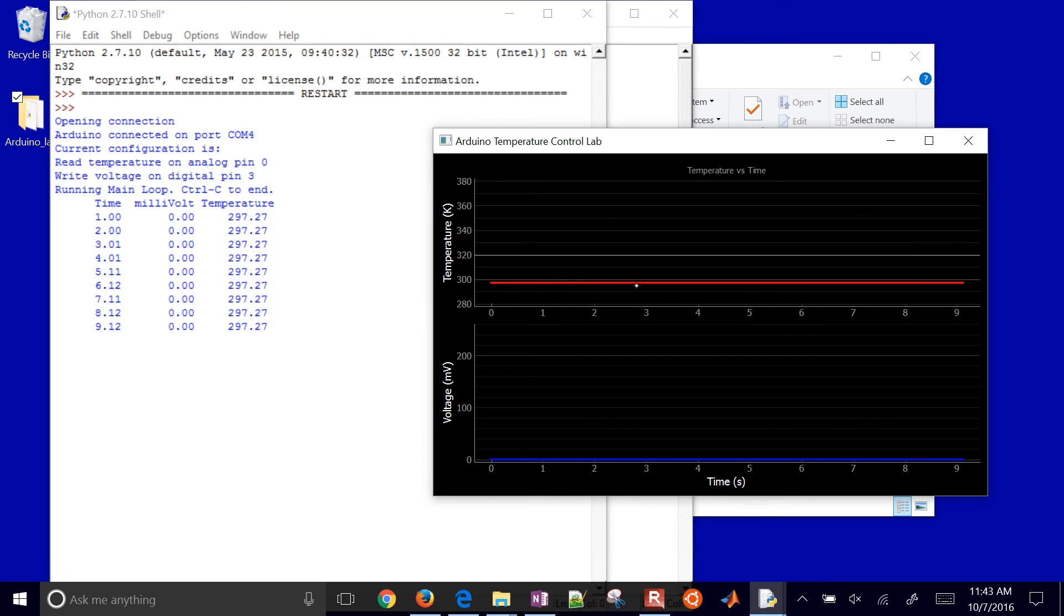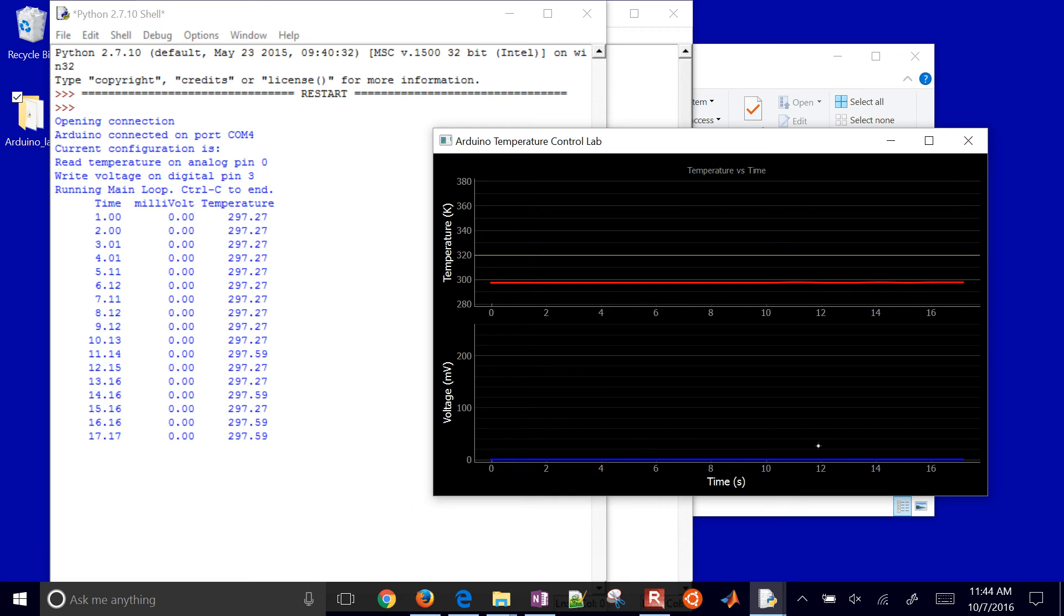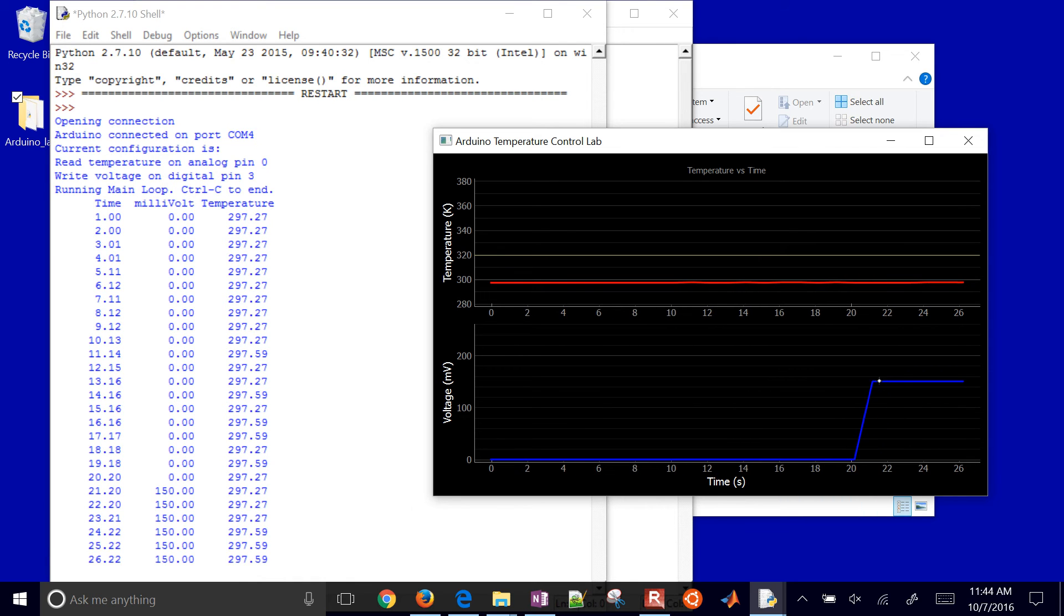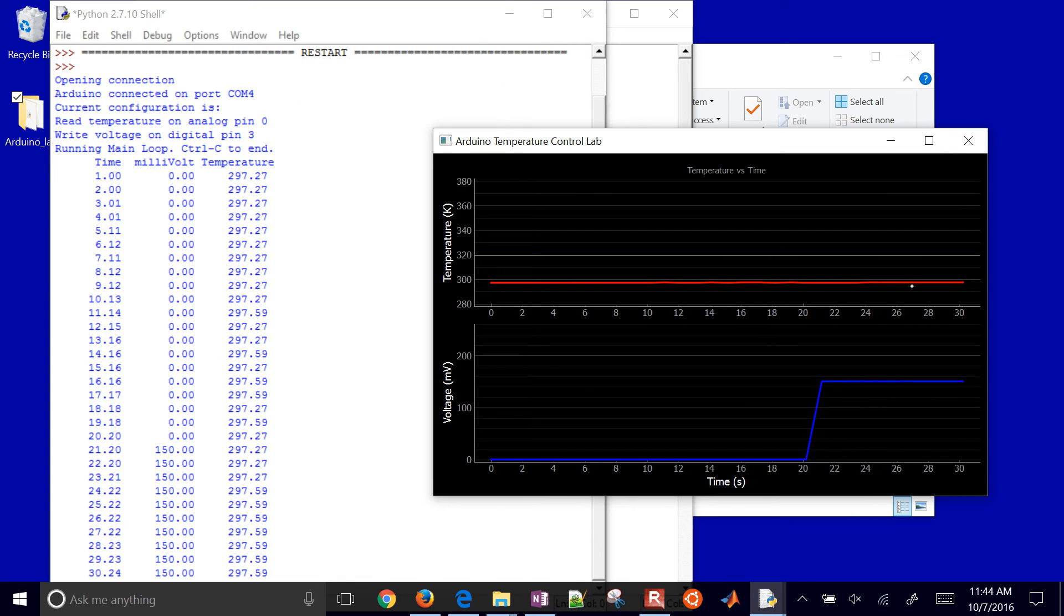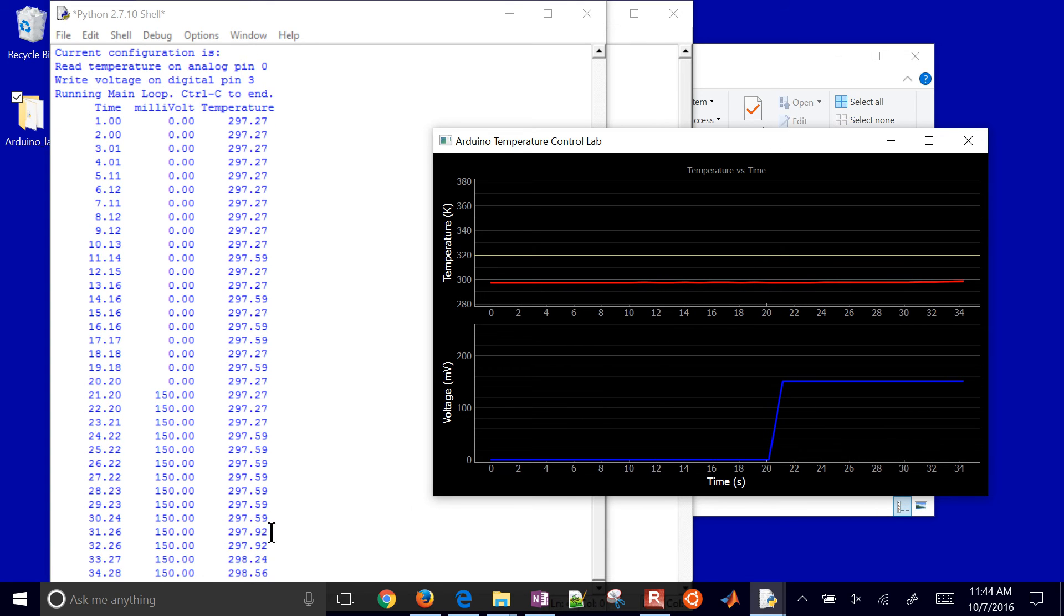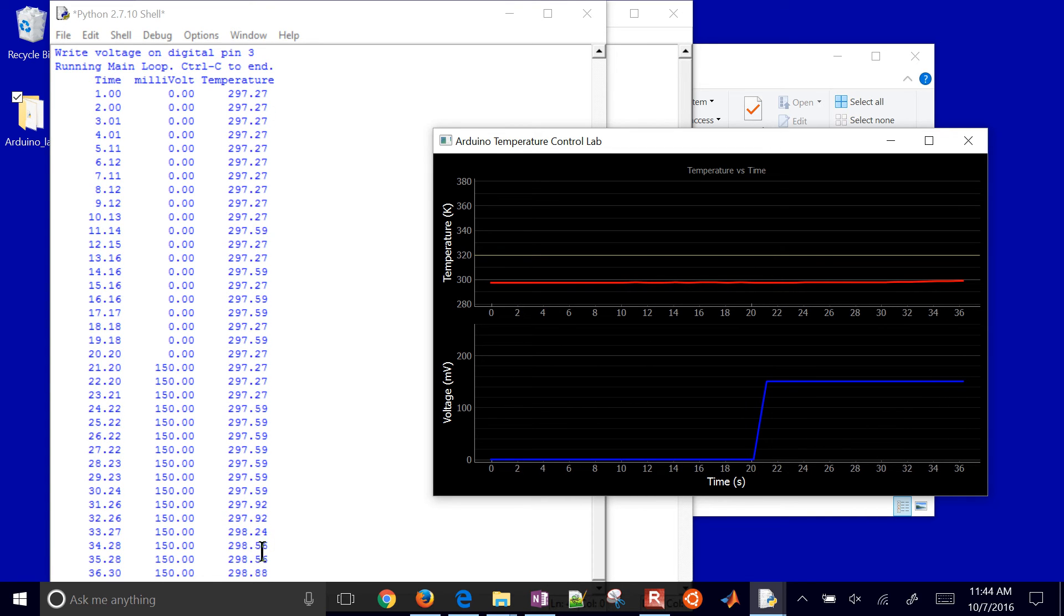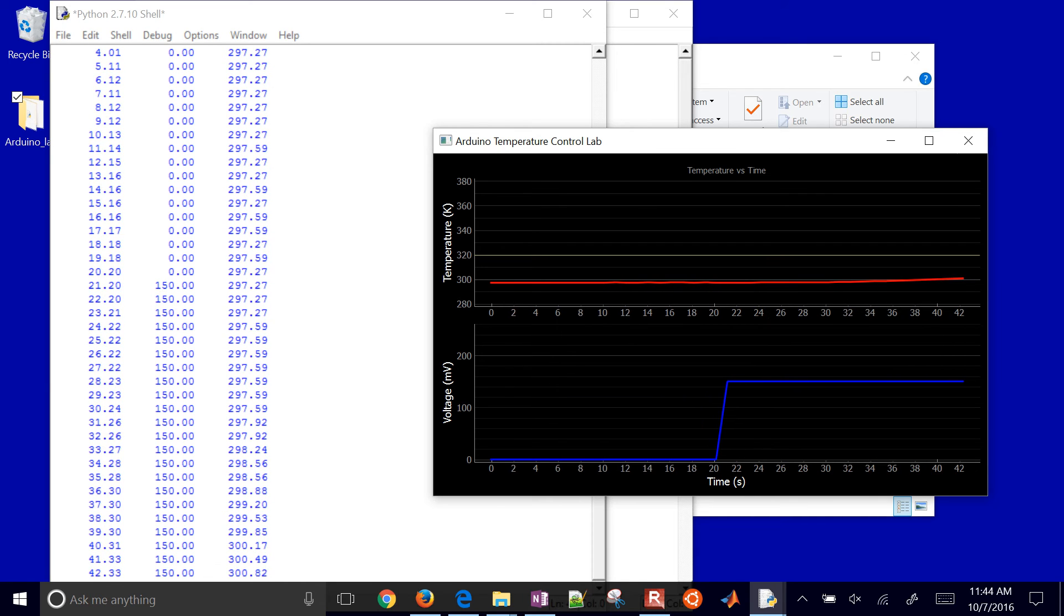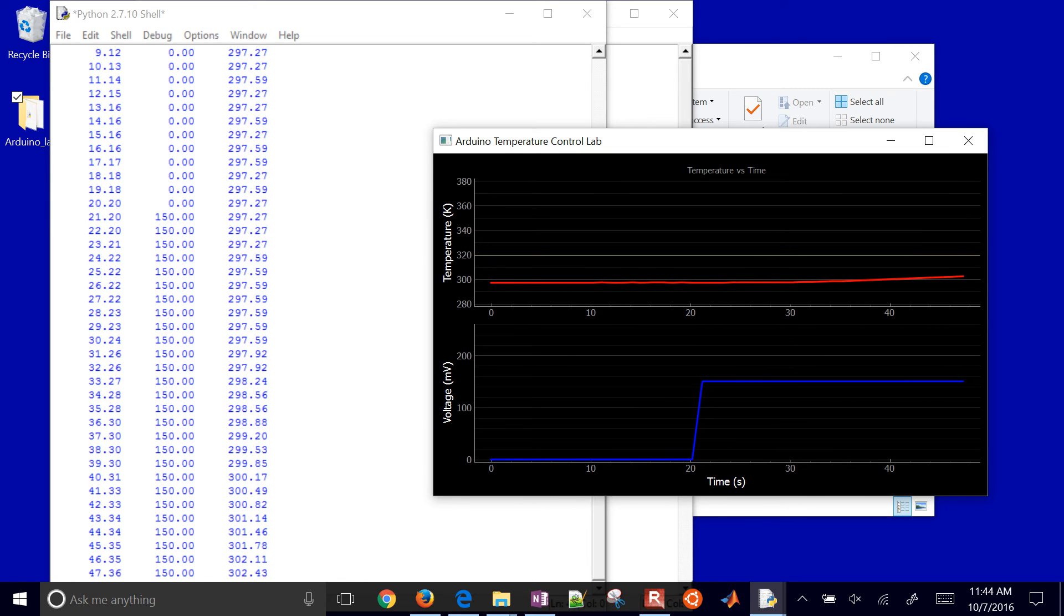And then it'll have this plot that starts up right here. You'll be able to see the red line. The red line is going to be your current temperature. The blue line is your millivolt signal. So if you either have a controller change that or you change it, the blue line is going to be your millivolt, and that just went from zero up to 150. And then what we'll see is we'll start to see this temperature rise. So you can see right here the temperature just went up by a degree. It's going up just ever so slightly there. You can see it rise just above 300, and it's going to continue to rise until it does our step response.